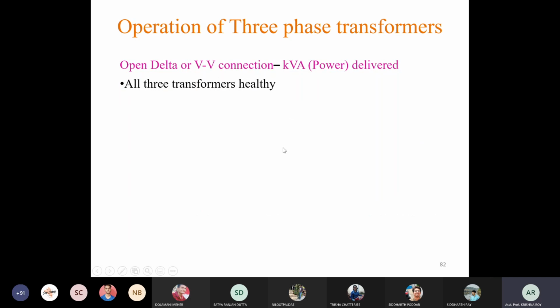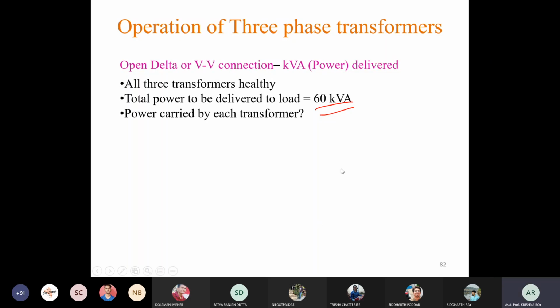Now the next is kVA delivered. Okay, so here let us consider one transformer bank which is having all the three transformers present. That means a three-phase bank with delta connection, and all the phases are healthy. By this transformer we can deliver 60 kVA load. Power carried by each transformer will be 1/3 of this 60 kVA, so that is 20 kVA.